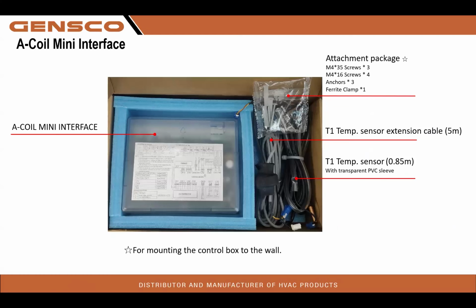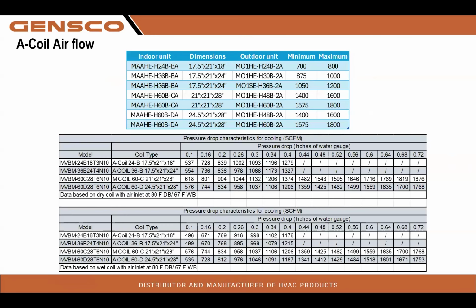There's a look at our mitigation control board that you are going to mount somewhere very close to the furnace installation. It's got screws. It's got sensors. It's got a sensor for T1 that is 5 meters long. It's an extension cable, but if you don't need a full 5 meters, 15 feet, we've got one that is roughly 3 feet long to install into the return air. Our static pressure drops and CFM, all of this information is in the install manual.